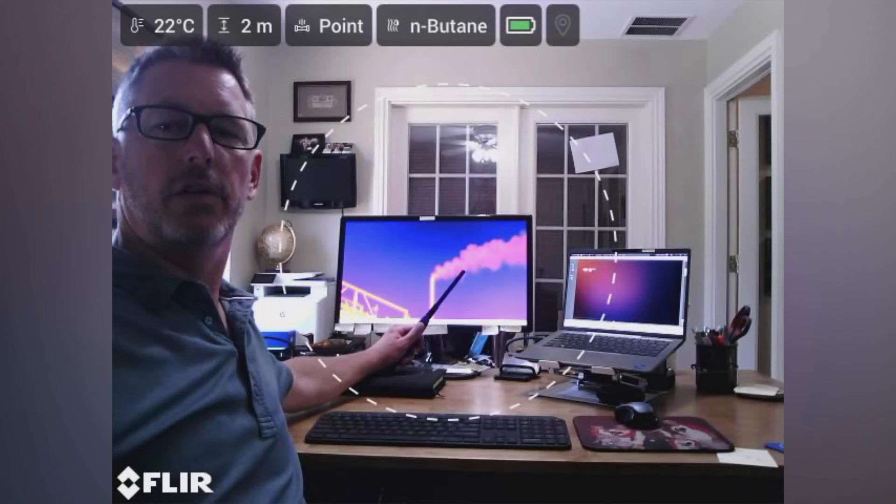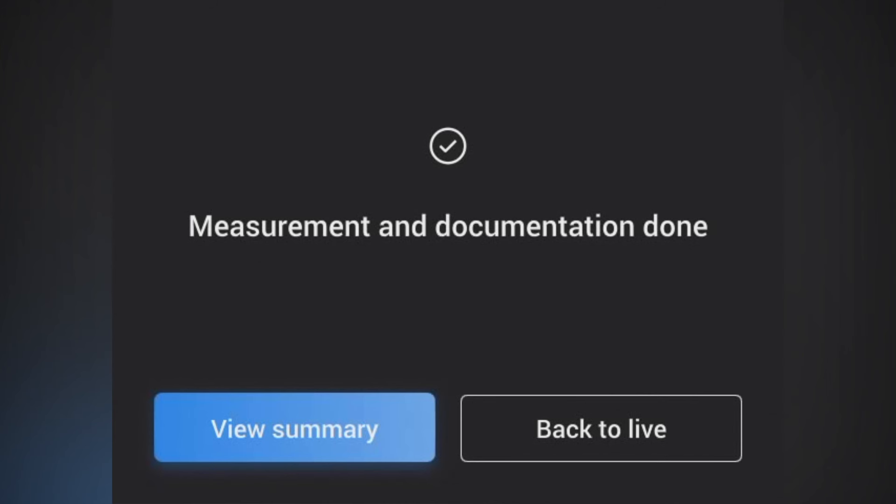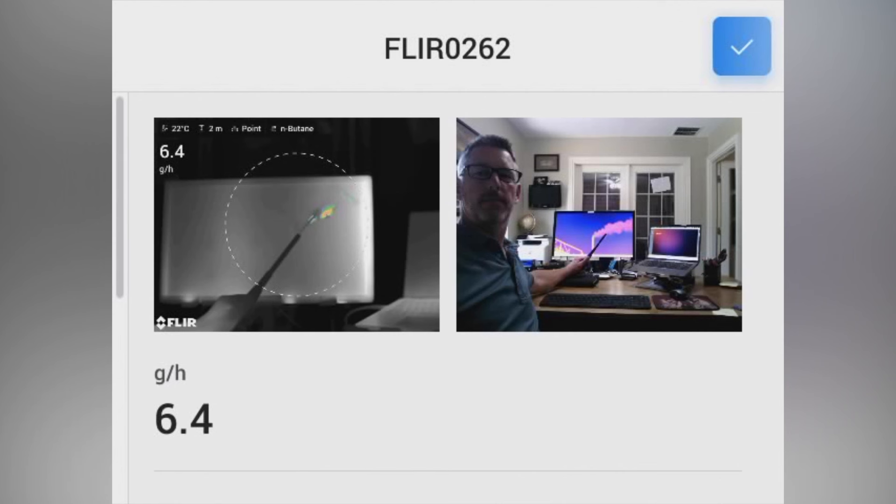In this case it'll take about 10 seconds to actually quantify, and when you're done it'll say documenting, show you a quick visual image of this, and then you'll have the option to view your summary. Here you can see the actual emission rate that we quantified in this case it was 6.4 grams per hour.